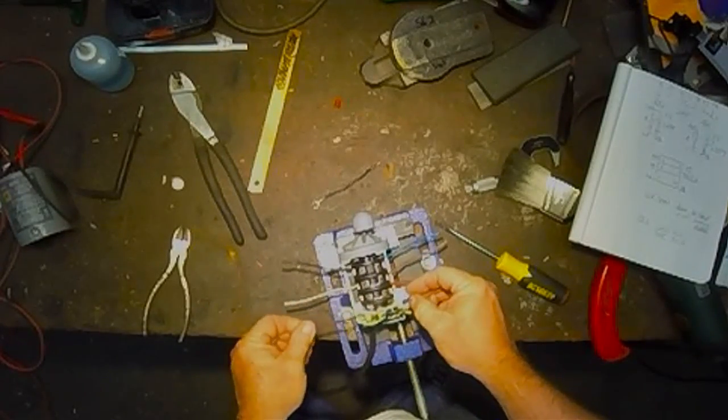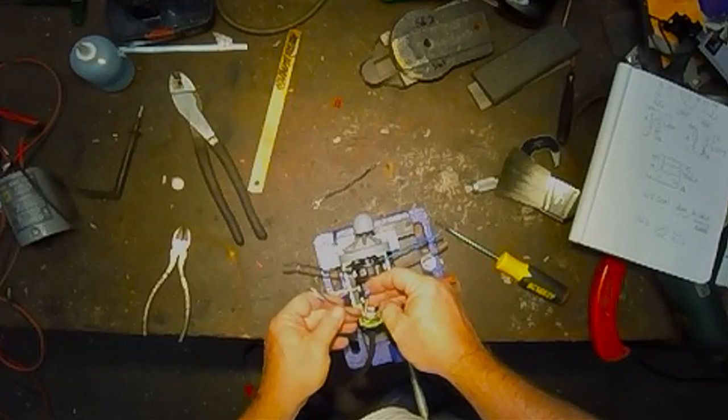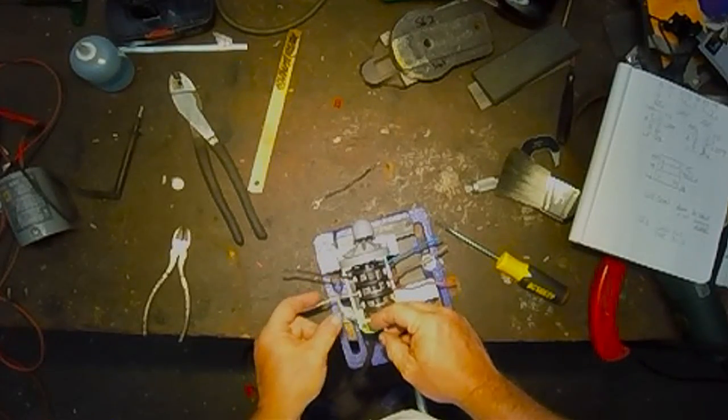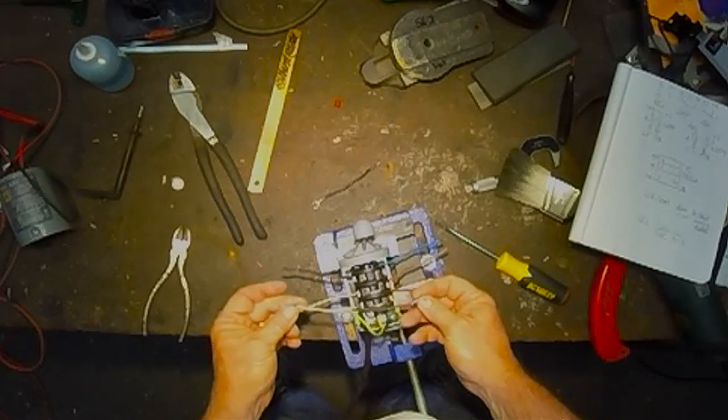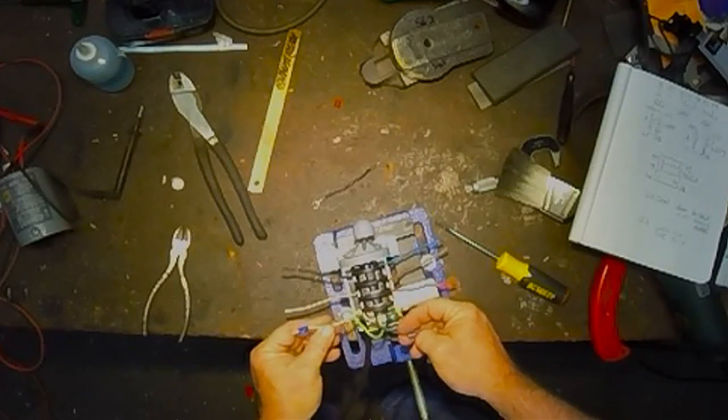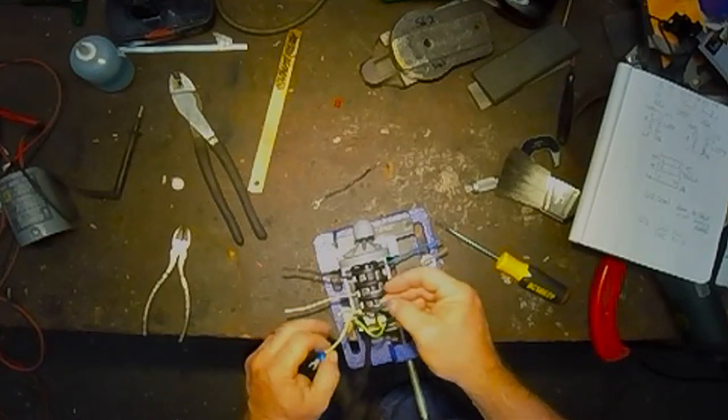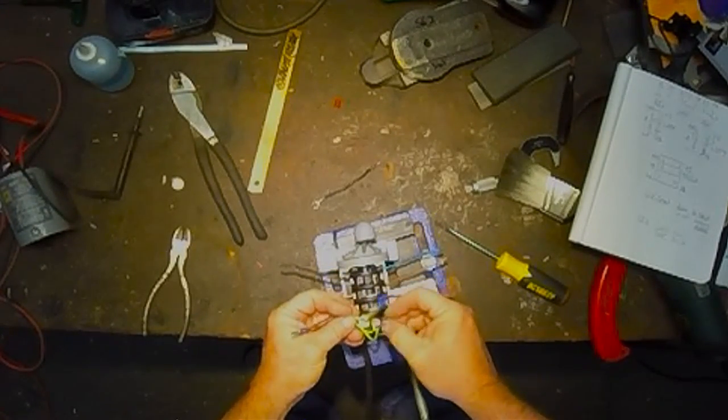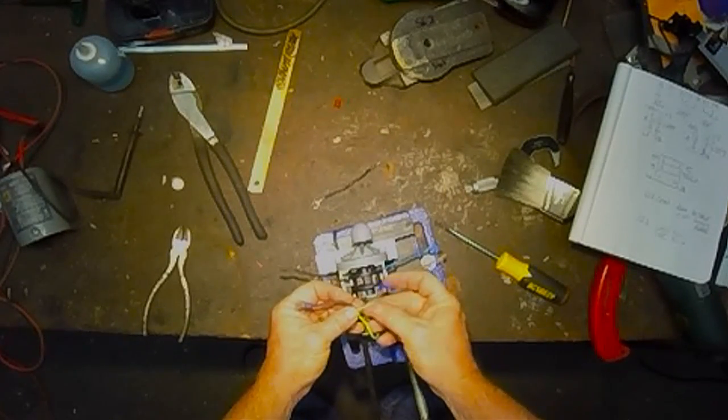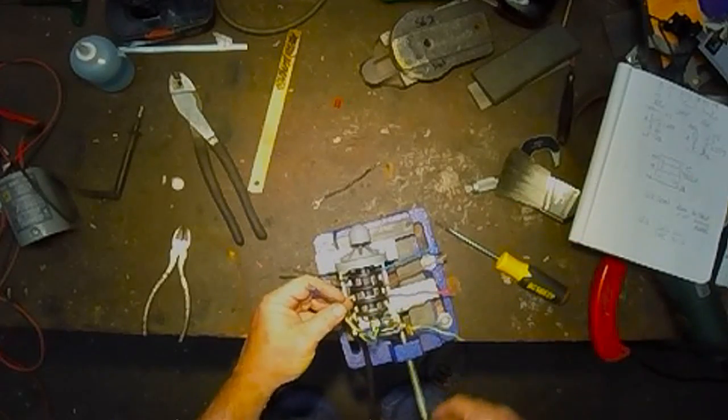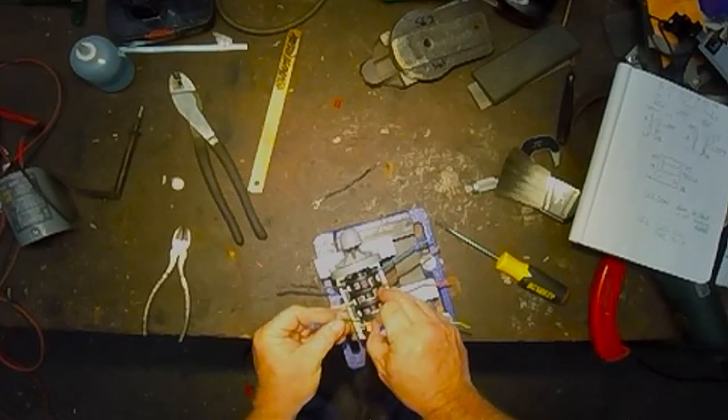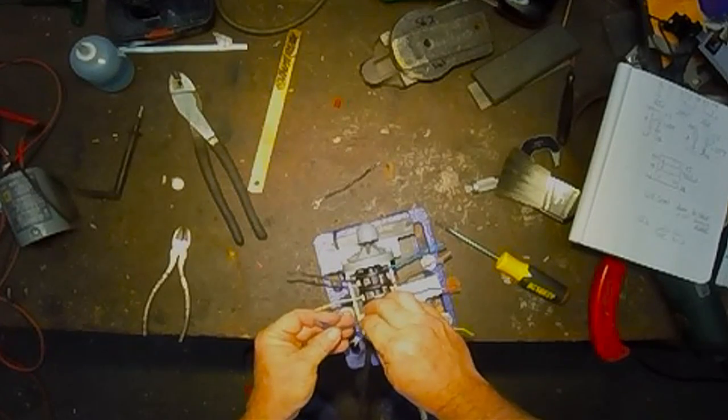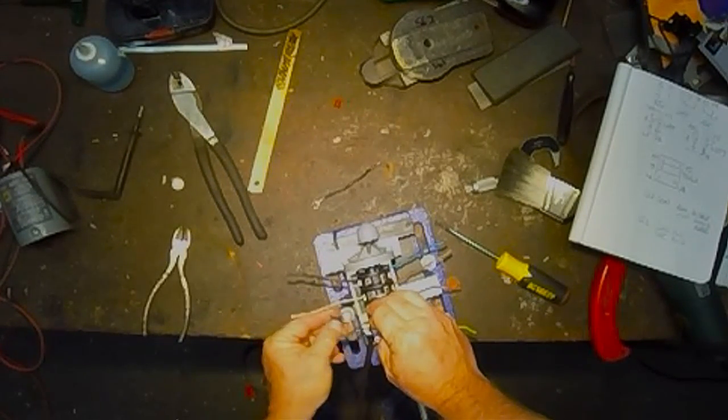Okay, so we got two wires left. In your service, you could probably use 14 gauge. If you could use red and black, that's optimum because that's pretty much universal for 220 volts, but I didn't have a piece of that handy. I get superstitious on it - I always like to make black L1 and when I'd normally be wiring 220 volts, I'd use red as my L2. Don't ask me why, that's just the way I've always done it. It really doesn't matter, you could swap either one and the motor will run.